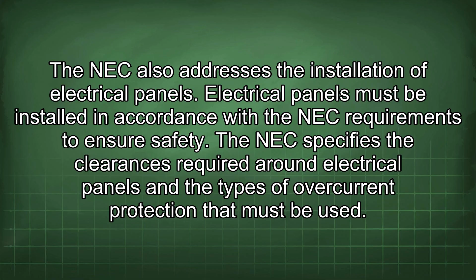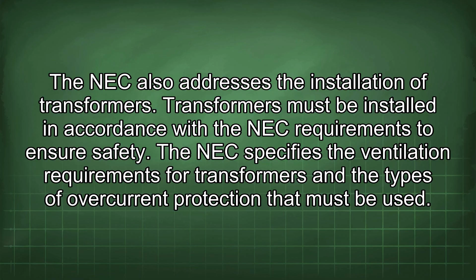The NEC also addresses the installation of transformers, which must be installed in accordance with NEC requirements to ensure safety. It specifies the ventilation requirements for transformers and the types of overcurrent protection that must be used.